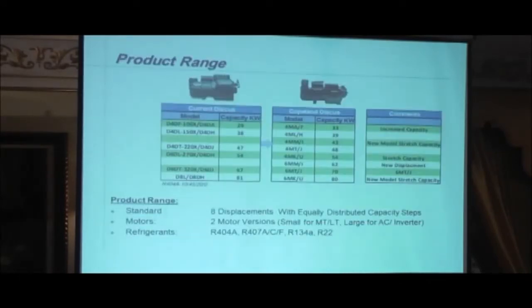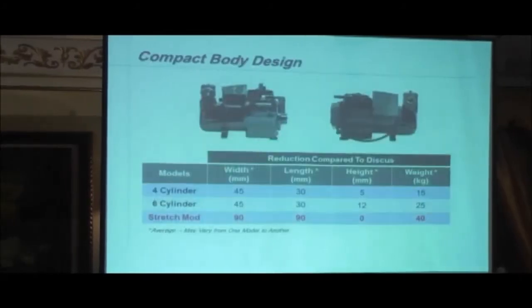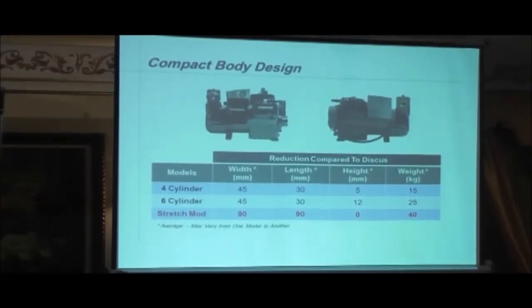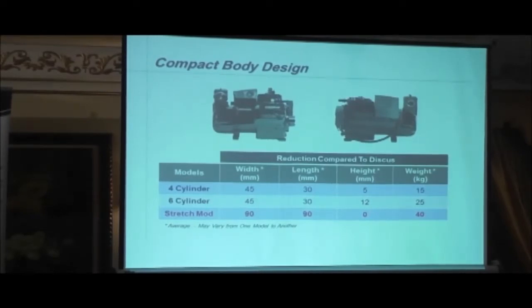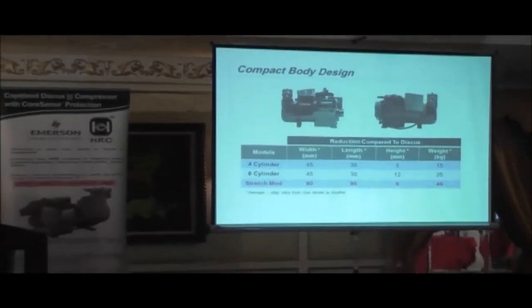So in this new range, we've got 8 displacements, and each displacement will have 2 motor versions. We use the smaller one for LT application, the larger one for HT or air conditioning. And again, as I mentioned before, the refrigerants, depending on application, we have codified the compressor for all the new refrigerants on the market. As I mentioned before, this is a new compact design. So if you compare the dimensions of Discus 3 with Discus 2, there are going to be some changes. Okay? You have a reduction in width, length and height, and also in weight.